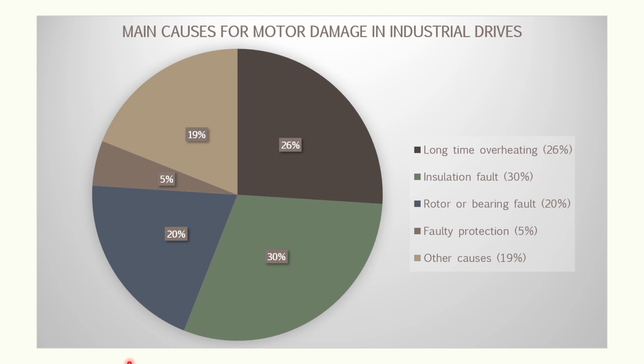This is the pie chart for main causes for motor damage in industrial drives, and as you can notice, 30% goes to insulation faults, followed by long-time overheating 26%, rotor or bearing fault with 20%, other causes 19%, and faulty protection 5%. As we go through my presentation, we can reason out why insulation fault got the biggest portion of the pie chart and the reasons for the other four main causes.